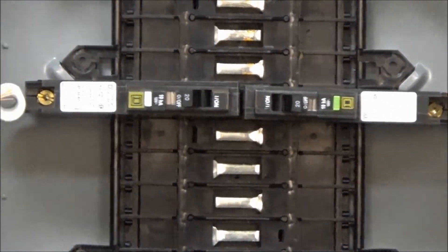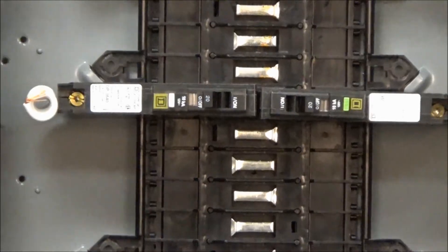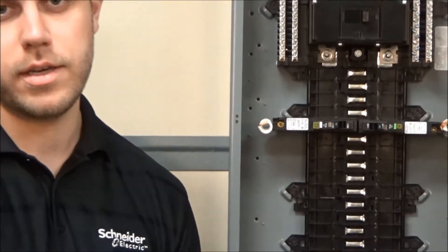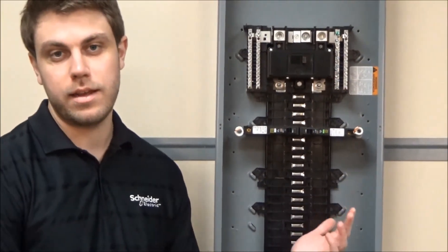These are used to detect parallel arcs. For example, if there is an arc between the hot and neutral of your circuit, this breaker is used to detect that and will trip.